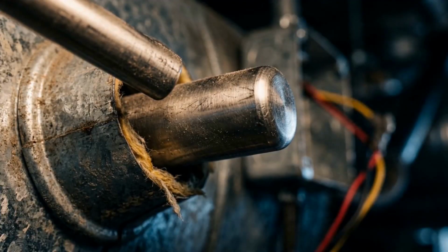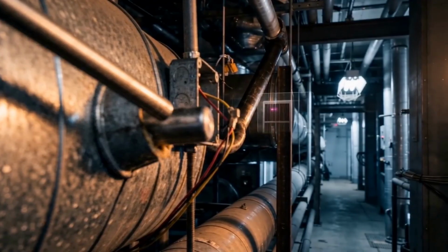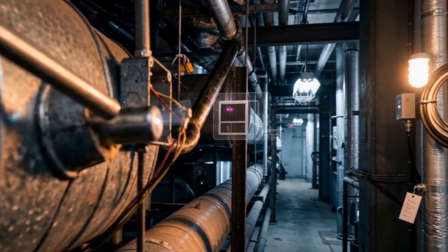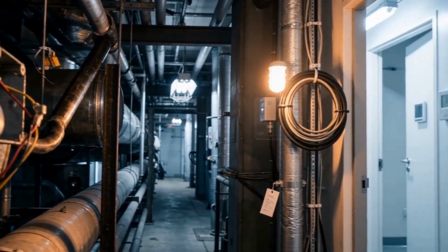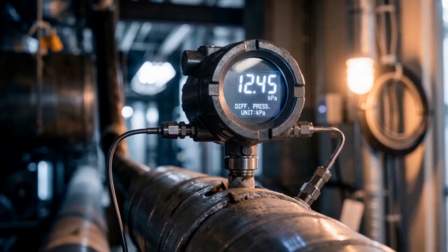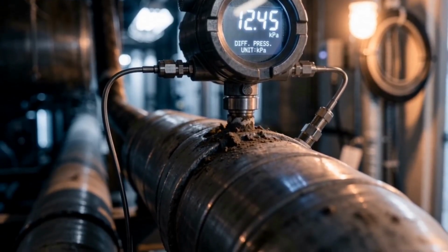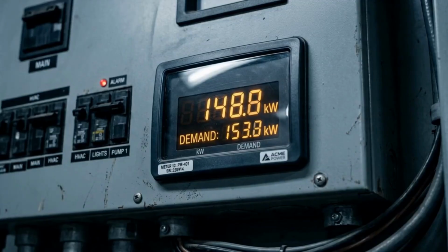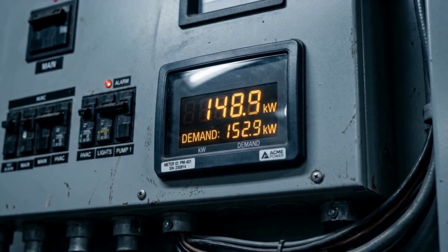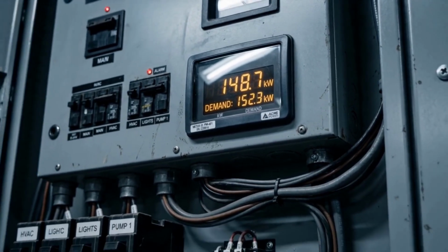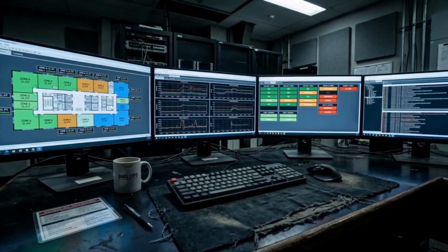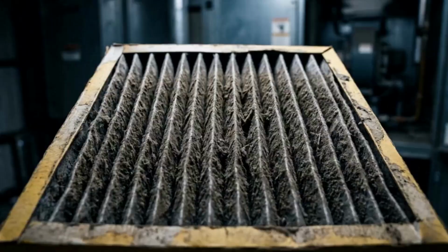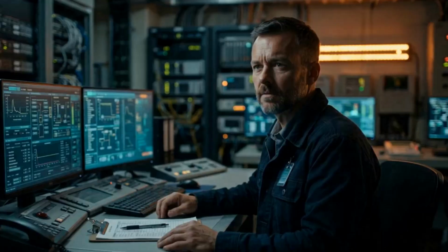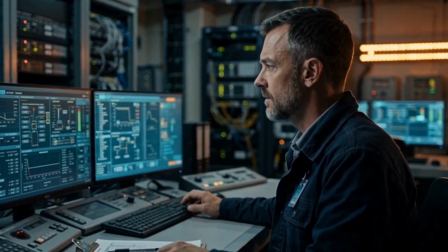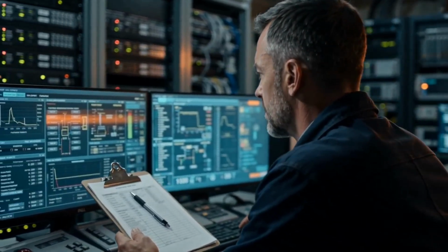What does the BMS read? Inputs from sensors. Temperature sensors in ducts, intakes, pipes, and occupied spaces. Pressure sensors for duct static and filter differential. Humidity sensors for sensitive spaces. Electrical meters reporting kilowatts and demand. And flow meters for chilled and hot water. These points show how air, water, and power are behaving. When a filter loads and differential rises, or demand spikes on a meter, the BMS sees it first, feeding operators data used for energy programs and fault detection.